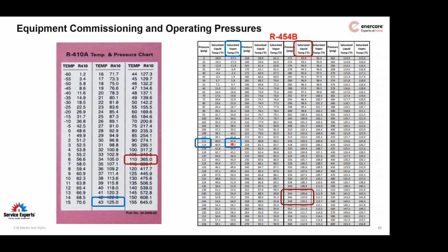43 degrees, give or take, for R454B on the vapor side. It's a little less, actually, about 10, 12 psig less. The pressure is actually slightly lower. And then same thing on the liquid side. So for 110-degree liquid temperature at 365 psi, which is actually kind of high for 410, you can see here that it's even a little lower. So instead of being, say, 365, you got like 346, give or take. So it's a little bit lower for R454B.